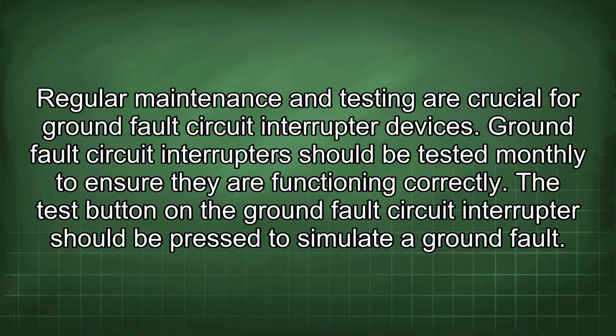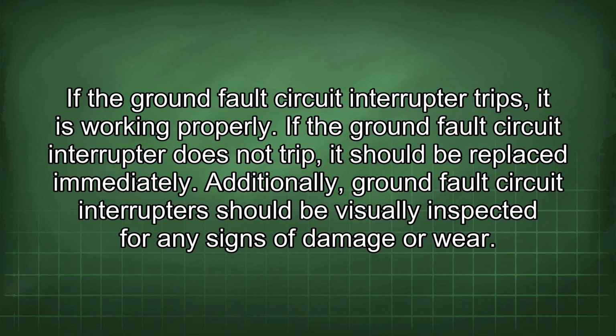Regular maintenance and testing are crucial for ground fault circuit interrupter devices. Ground fault circuit interrupters should be tested monthly to ensure they are functioning correctly. The test button on the ground fault circuit interrupter should be pressed to simulate a ground fault. If the ground fault circuit interrupter trips, it is working properly.